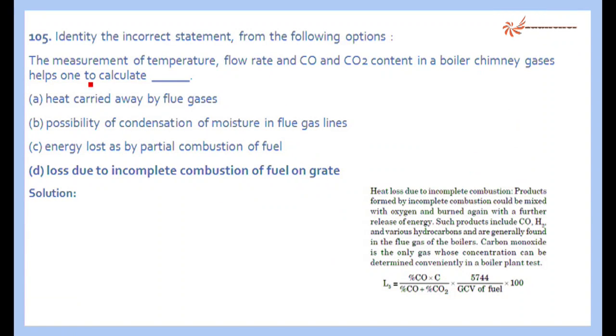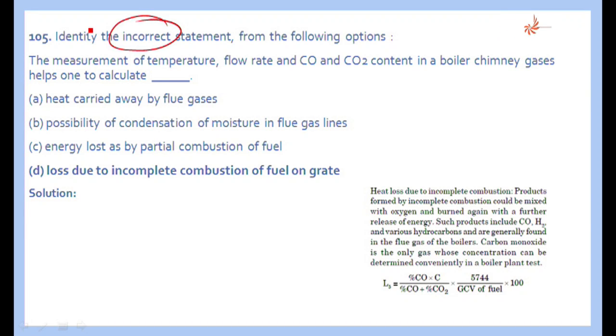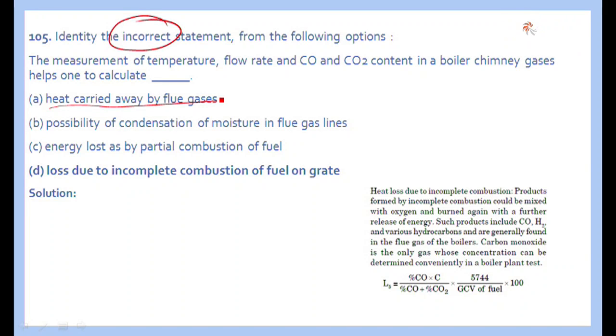The next question: measurement of temperature, flow rate, and CO and CO₂ content in boiler chimney gases helps one to calculate which of the following. It can help find the heat amount of flue gases, the possibility of condensation of moisture in flue gas lines, and energy lost by partial combustion of fuel — since incomplete combustion generates CO, hydrogen, CO₂, and other hydrocarbons. Option D — loss due to incomplete combustion on the grate — is the incorrect answer.